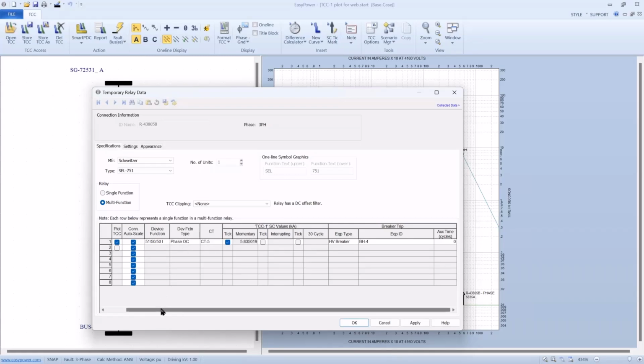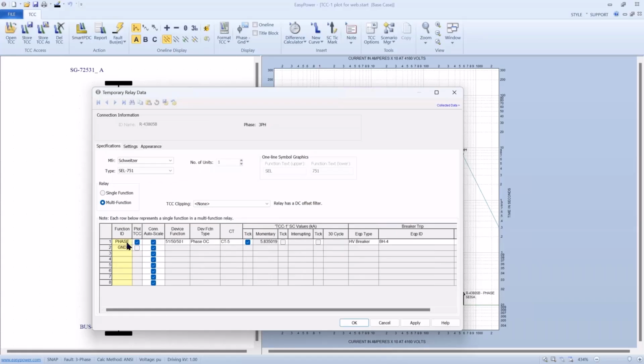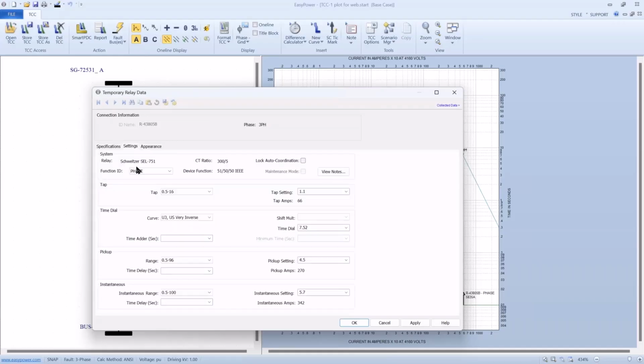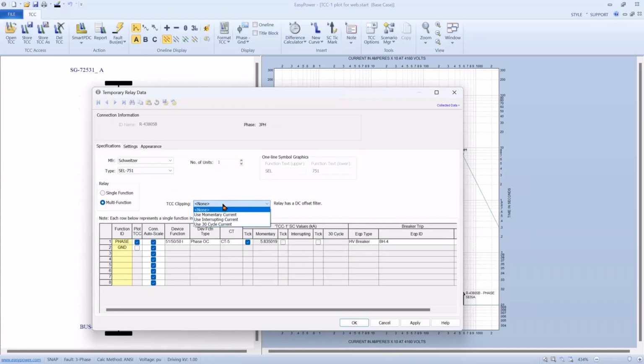In addition, instead of just using numbers, we're using the mnemonics phase and ground for each of my functions. So if I go look at settings for the phase element, this is an issue with the instantaneous set where it is, because it's going to be tripping pretty fast and at relatively low current. So there are two things I'm going to do that I may want to go back and check later on. I'm going to disable instantaneous. I want to go back to my specification and make sure I'm not clipping the TCC plot. Once I get things coordinated, I may want to go in and clip, especially at interrupt current, but for now I'm going to leave it undone.